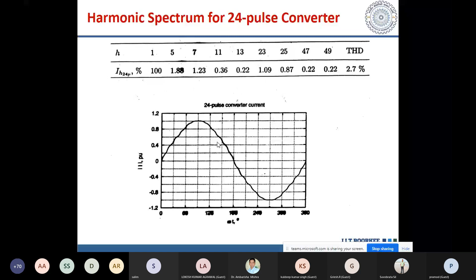First let us complete this. Even if your DC side current is constant, you can have either a quasi-square if it is a star-star, or if it is a delta-star, a 6-step waveform. Both are non-sinusoidal. But when we talk about the harmonics, it's not necessary that we should always talk about an individual application. In any industry, there might be multiple drives in use, all drawing current from the supply, and those converters might be operating at different firing angles. So the net current drawn from the supply by that industry as a whole may be different from the individual current.